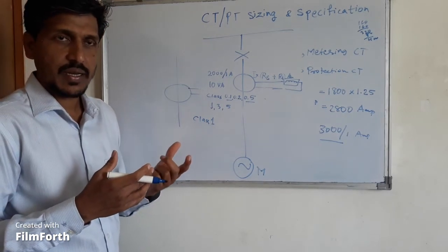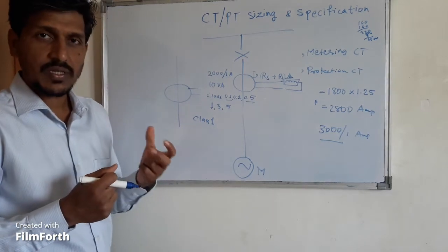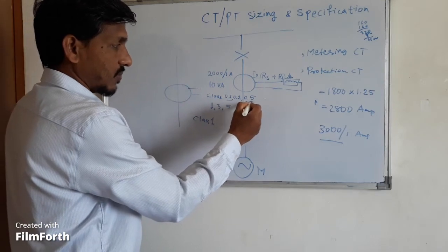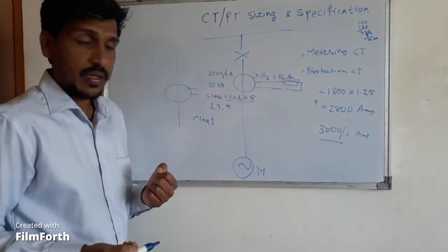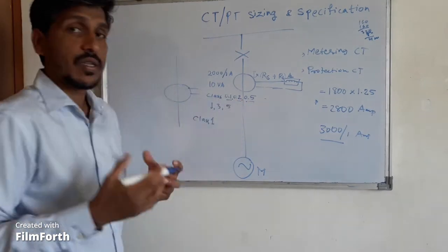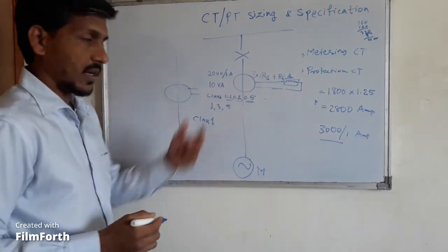Any energy metering company like MSEB has to measure the feeder, how much is the energy consumption. So we will go for class 0.5 because they want accuracy of 0.5 or 0.2. In laboratories, they normally use 0.1 or 0.2 because their accuracy is much more important. For an energy company, it is 0.5 class meters.